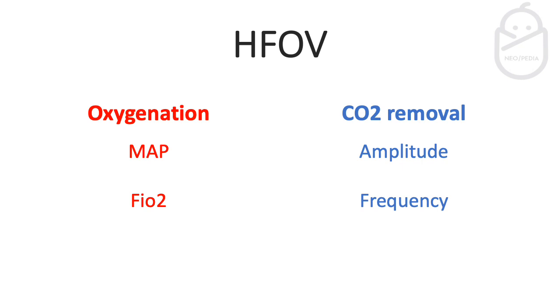The main difference between high frequency oscillation and conventional ventilation is that in conventional ventilation, changing the PIP affects both oxygenation and CO2 removal simultaneously. In HFO, you have two separate entities. To control oxygenation, you have two elements: the mean airway pressure (MAP) and the FiO2 — how much oxygen you're giving to the child.